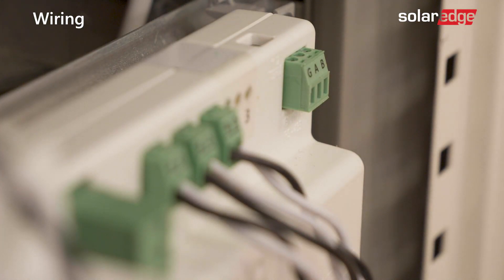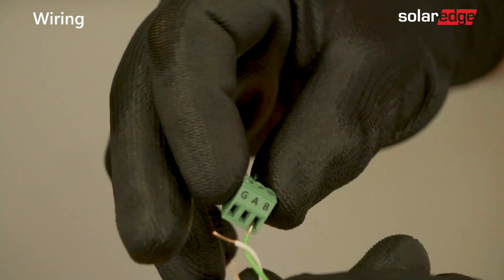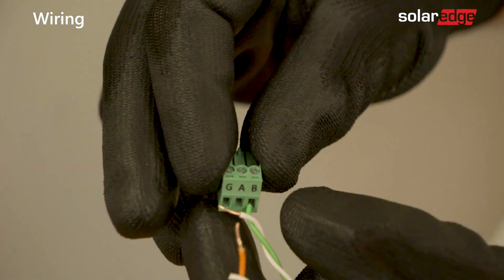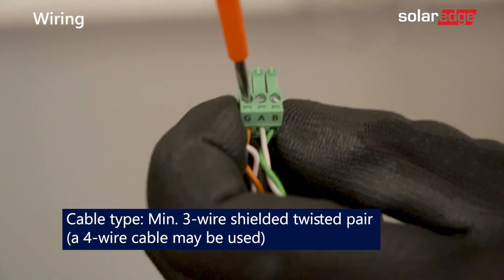Next, pull out the RS-485 connector located on the communication board. Then, connect the RS-485 wires to the A and B terminals, and connect the shield to the G terminal.